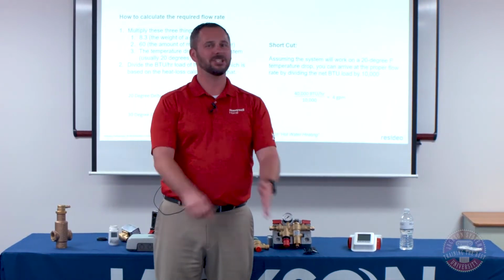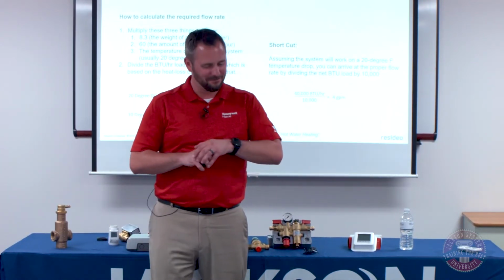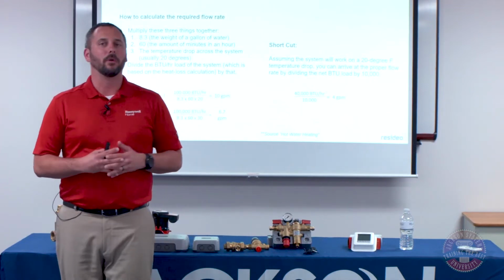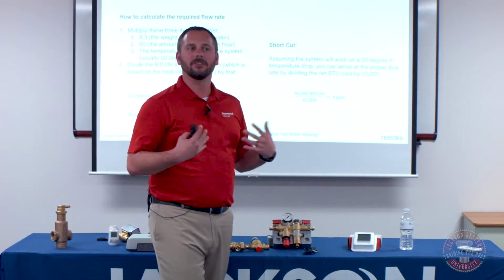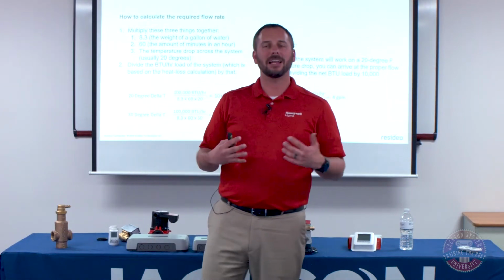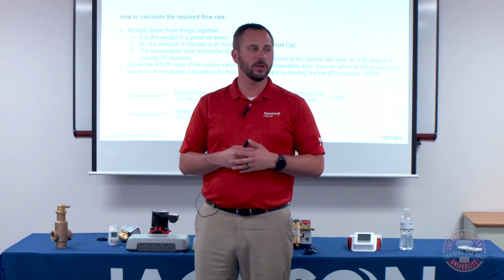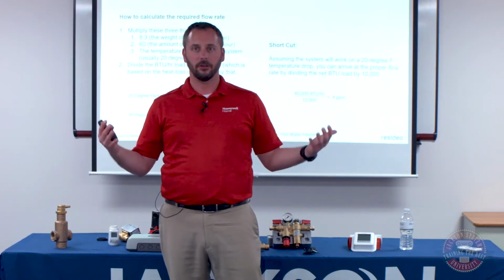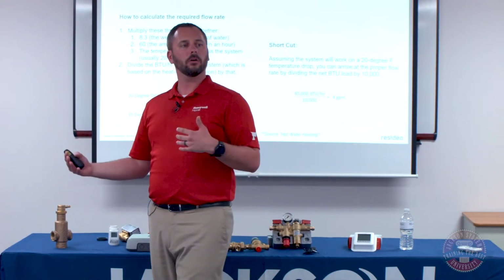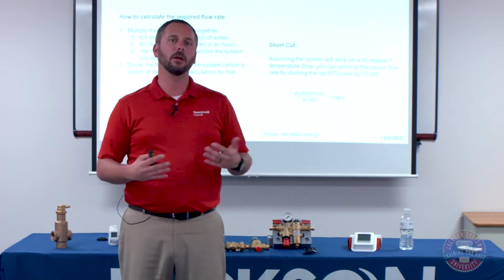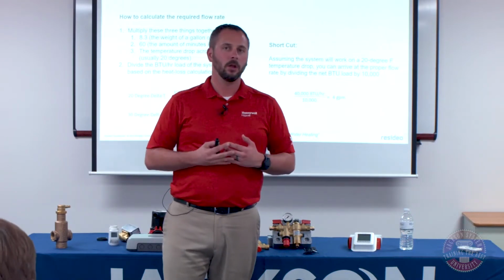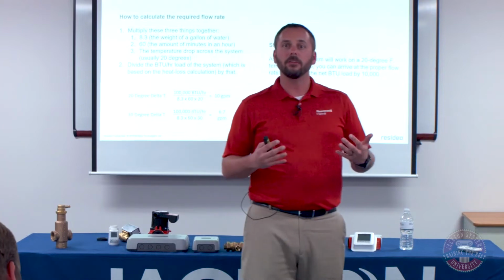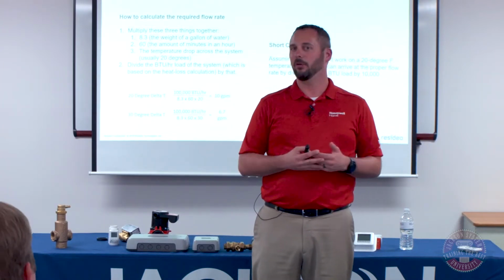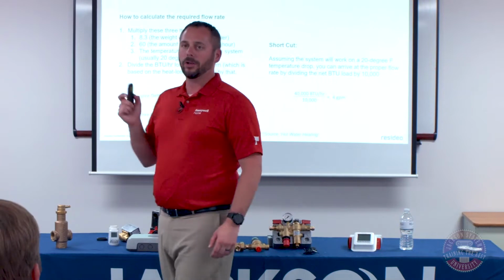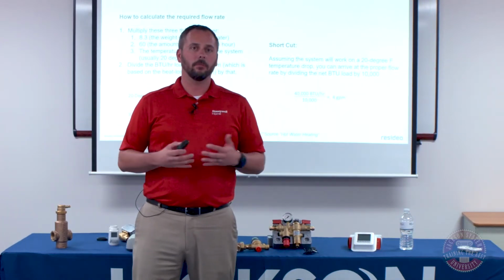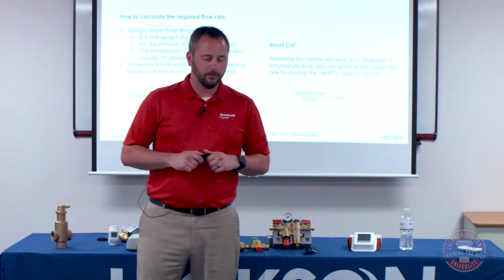And I apologize because all my cheat sheets are down at the ground, so I'm going to be looking down at them. So when you're coming up with flow rate, so let's say you're going into a job site that's got an existing boiler, or you have a rough idea of the area that it's serving. Because we could be doing a pump to serve the entire system with zone valves, or some people prefer to do what's called zone pumping, where you're going to have a pump on every single loop. There's pros and cons to both methods. My goal is to prep you so you can handle anything that you walk into. So when you're looking at the pump and the system, you need to come up with the flow rate first.